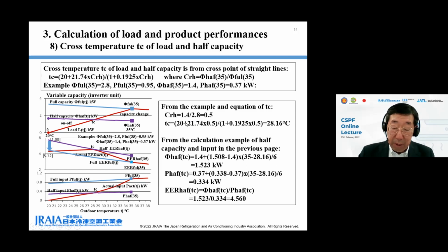The upper and middle figures in this page are the same as the figures for the variable capacity unit in the previous page. The lower figure shows full, half, and actual input at each outdoor temperature Tj. By entering CRH 0.5 in the equation, the cross temperature Tc for this example becomes 28.16 degrees C.